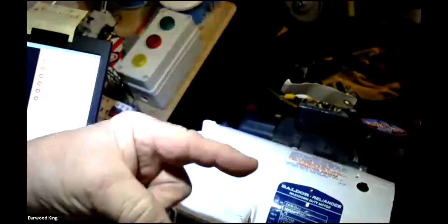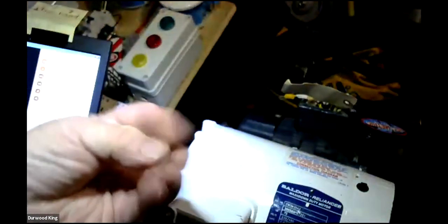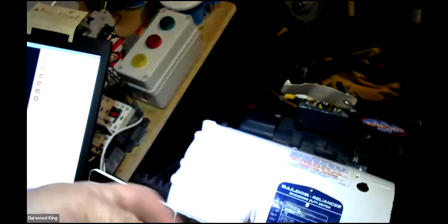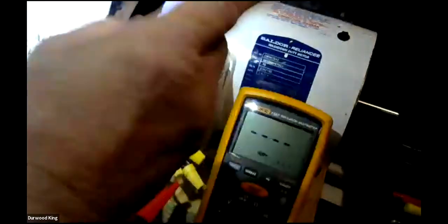If the motor is just crawling, making a single-phase groaning noise, or just humming, but all of the voltages are there, that's an indication that you may have an open winding. If you check each lead to ground and then phase to phase, and all the voltages are there, yet the motor doesn't behave right, then you want to check internal resistance that way, and that's going to tell you if you have this.